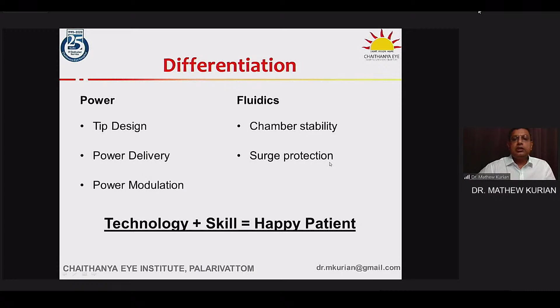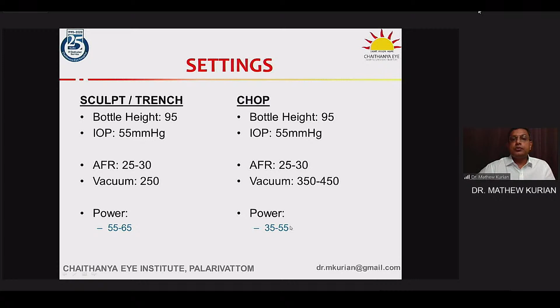The settings that I use for sculpt are a medium bottle height or IOP, now on the Centurion system, of about 55. The flow rate is around 25-30. Vacuum for sculpting is lower and the power is moderate to high. In the chopping settings, bottle height and IOP don't change too much. The flow doesn't change, but I go to a slightly higher vacuum and I actually reduce the power. I'm using more of a flow-based chopping technique.